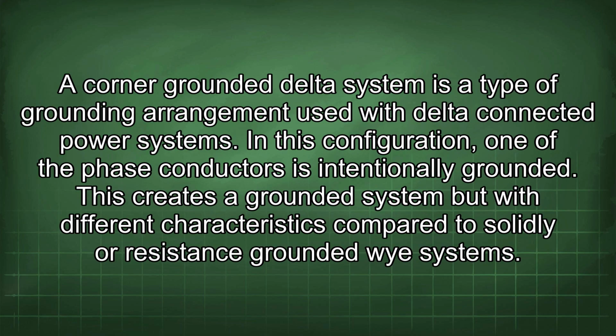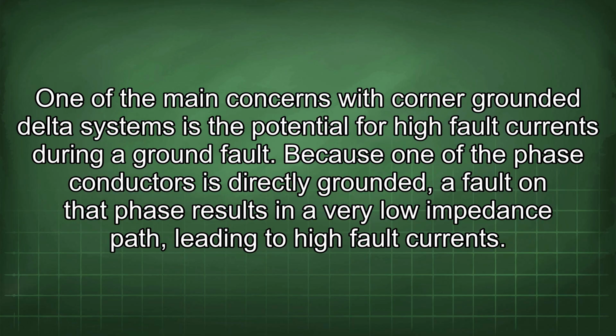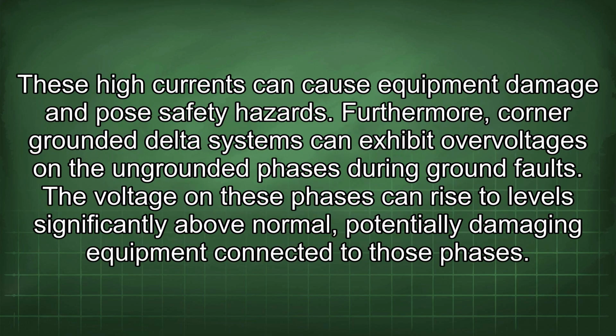A corner-grounded delta system is a type of grounding arrangement used with delta-connected power systems. In this configuration, one of the phase conductors is intentionally grounded. This creates a grounded system but with different characteristics compared to solidly or resistance-grounded Y systems. One of the main concerns with corner-grounded delta systems is the potential for high fault currents during a ground fault. Because one of the phase conductors is directly grounded, a fault on that phase results in a very low impedance path, leading to high fault currents. These high currents can cause equipment damage and pose safety hazards. Furthermore, corner-grounded delta systems can exhibit overvoltages on the ungrounded phases during ground faults.